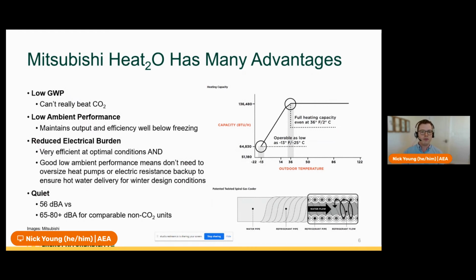So for example, if you had a design temperature of 36 degrees for your plant, well, the Heat2O is not going to lose any of its capacity at 36 degrees Fahrenheit. And so you know that the nominal rated capacity is going to be your capacity at design conditions. Whereas, some other traditional refrigerant products, their capacity might be cut in half or worse as you approach freezing.